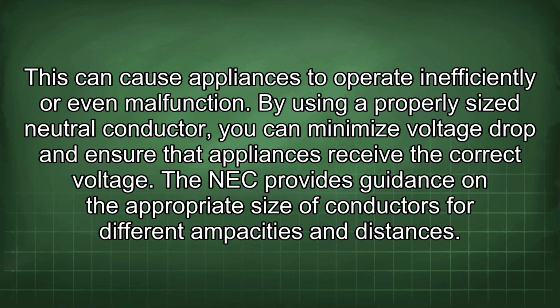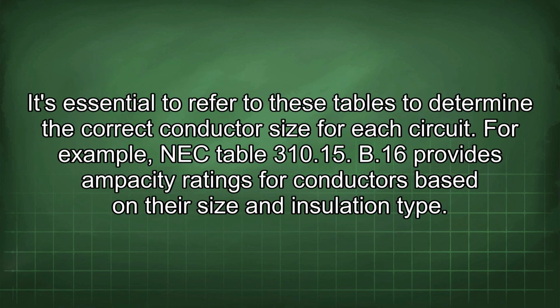The NEC provides guidance on the appropriate size of conductors for different ampacities and distances. It's essential to refer to these tables to determine the correct conductor size for each circuit. For example, NEC Table 310.15.B16 provides ampacity ratings for conductors based on their size and insulation type.